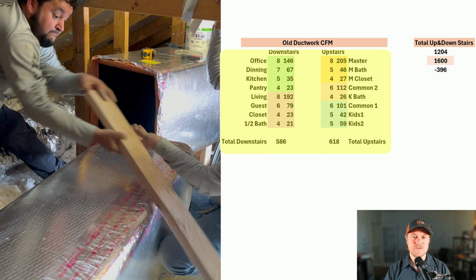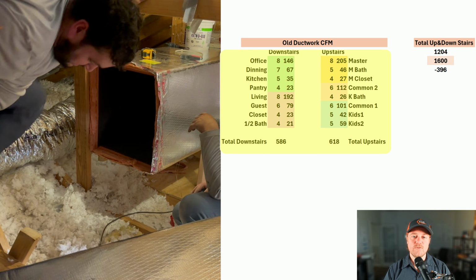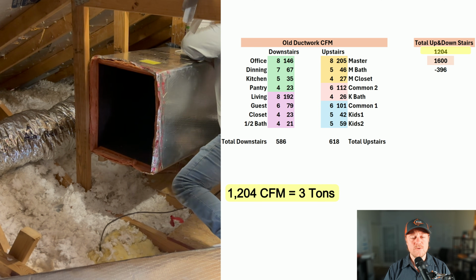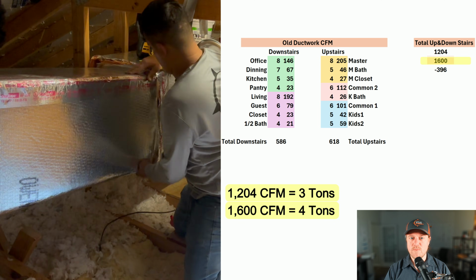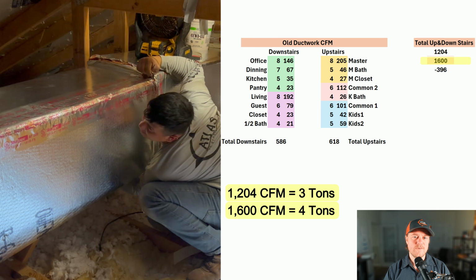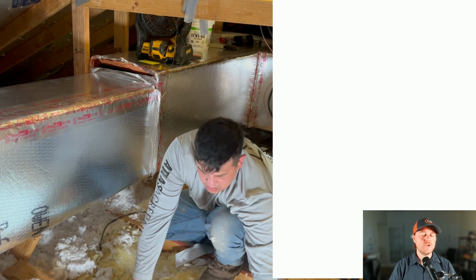The upstairs and downstairs, whenever I combine the CFM, it is delivering around 1200 CFM, even though the system is pushing 1600 CFM. So I'm only getting 3 tons of airflow out of it on a 4-ton system. I'm going to do 2 CFM tests.